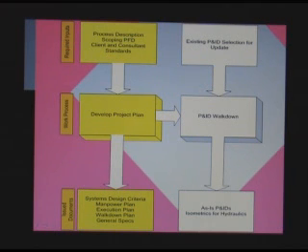Now, in the meantime, there was no new legislation, so some of those refineries, most of them, all of them, have not updated their P&IDs. So when we get a new project, we take those P&IDs, and if you go and look at the plant, P&IDs no longer fit.